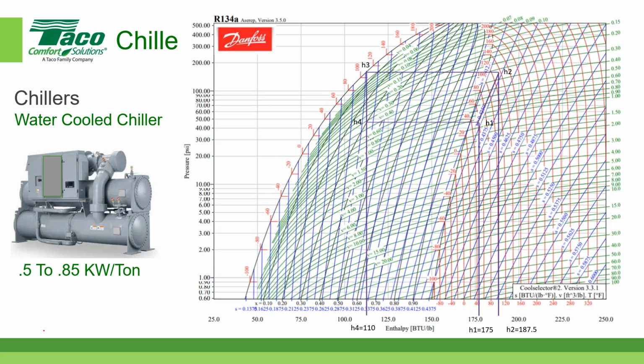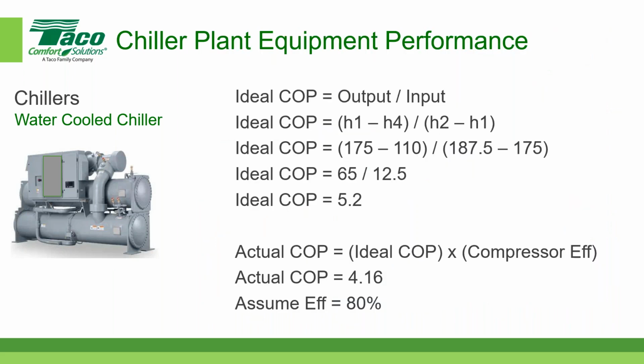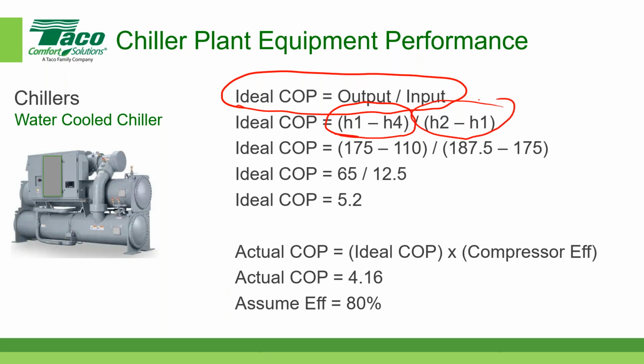Okay. So if we plug these numbers into these very simple equations, again, you're going to be able to have your recording so you can look at this little slide for as many hours as you like. But it turns out that the coefficient of performance is defined by the output divided by the input. And the output is the output of the evaporator, which is this value here. Input of the compressor is this value here. We just plug in the numbers that I had from that previous page, and we take the ratio of those two, 65 divided by 12.5. The ideal coefficient of performance is 5.2.